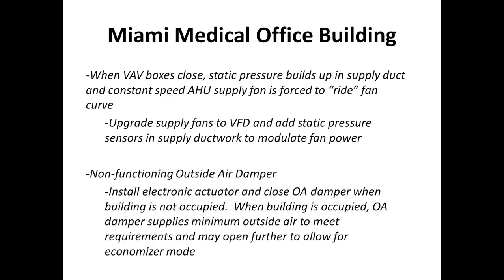As for the non-functioning outside air dampers, many of them were stuck in the open position, so the air handling unit was essentially pulling in outside air at all hours of the day, even when it was 95 degrees out and 65 to 70% relative humidity. By installing electronic actuators at these dampers, we could limit the amount of outside air that came into the building.